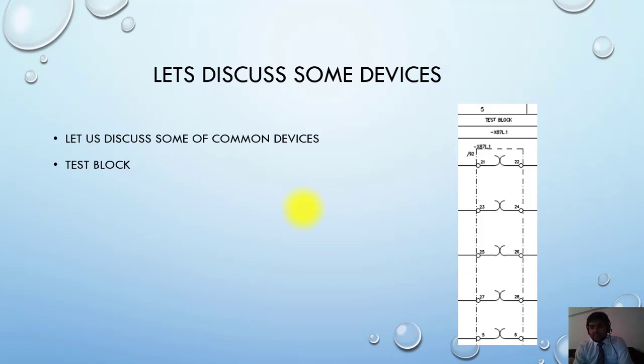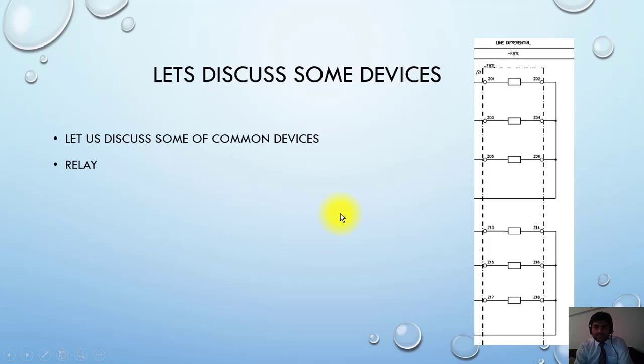Next is the symbol for a test block. This is named as X87L.1. 87 that we have seen is for differential. So this is a test block for differential relay. What is the function? Just brief information. You have to insert a plug here. The plug will isolate 21, 22 and these points, and then you can inject different quantities into the relay to simulate a fault. This F87L is basically a differential relay, and these are the current inputs shown here for one side, and this is the current input for another side. You can see here the terminal numbers are also mentioned.